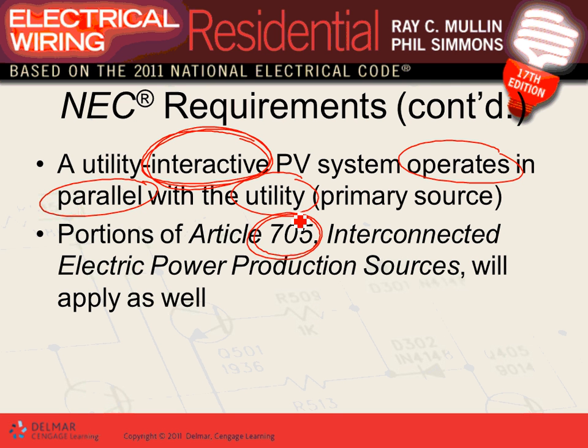They have electronic protection inside the inverter where it's constantly monitoring the voltage coming from the grid. And if the voltage coming from the grid goes to zero, what happens? We lost the grid. It shuts down the inverter. That's the only way right now that you can run an interactive system with the utilities. Requirement by codes, requirement by electrical utilities.